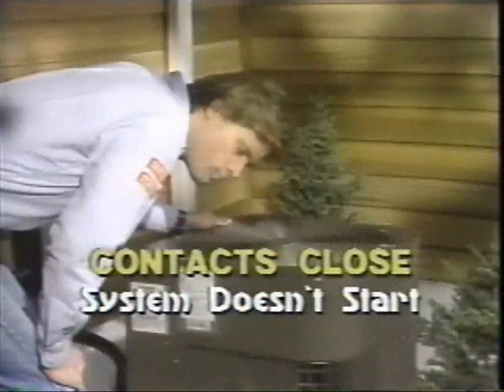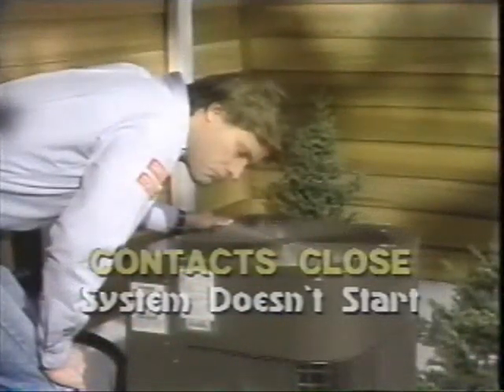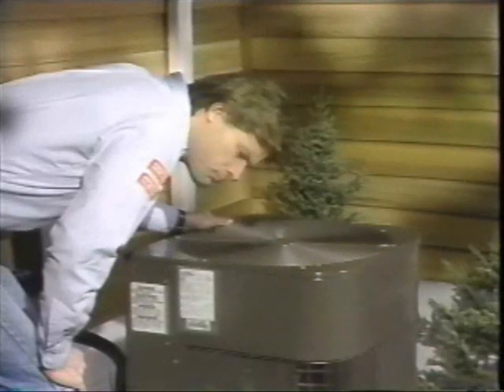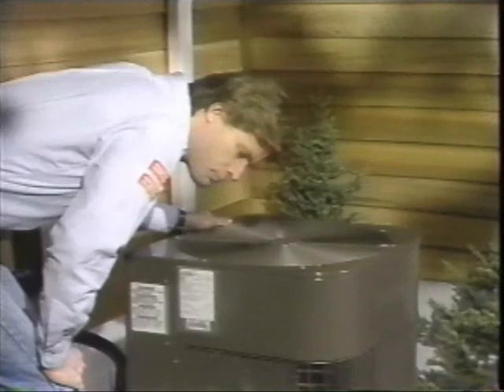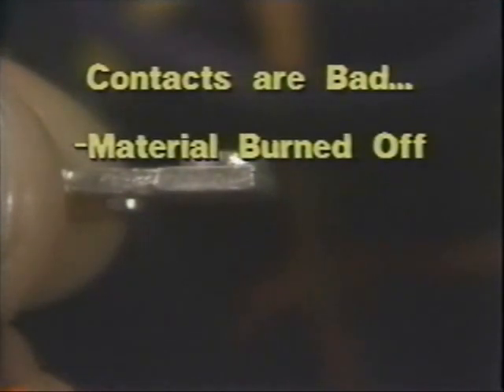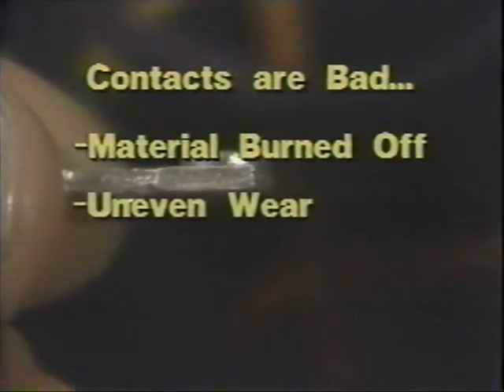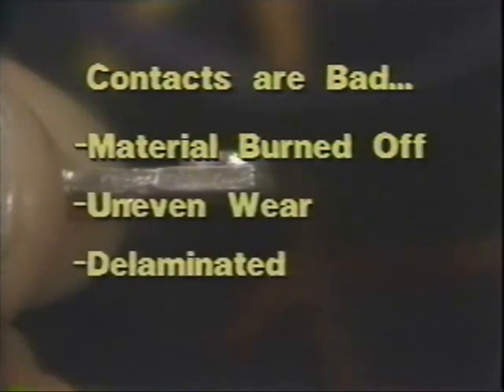If the contacts close and the system does not start, listen to the compressor motor. If it hums but doesn't run, most likely the problem is in the equipment, not the contactor. Normal contacts are either clean or black. You should see a uniform wear pattern. A speckled appearance is normal. Contacts are bad if excessive material is burned off. They show a pattern of uneven wear, or they are delaminated or peeled.